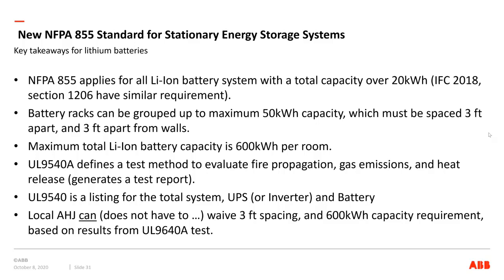What's also part of 855, as I mentioned, is that the battery can be tested according to UL 9540A. And 9540A is not a listing, it's a testing method. It tests at cell level, battery level, cabinet level, and total system level. You have to force a thermal runaway in one of the lithium-ion battery cells and prove that it does not propagate to other cells or other cabinets. Lithium-ion manufacturers have to do this testing.